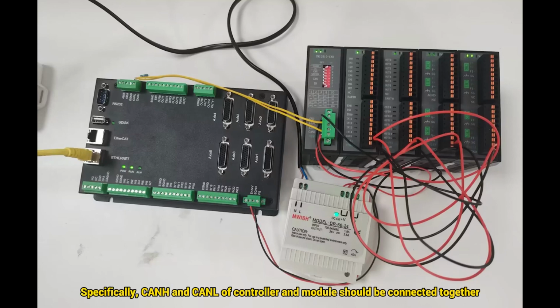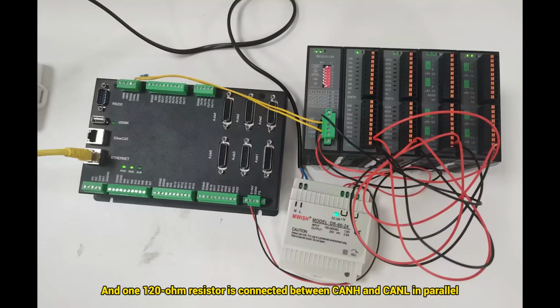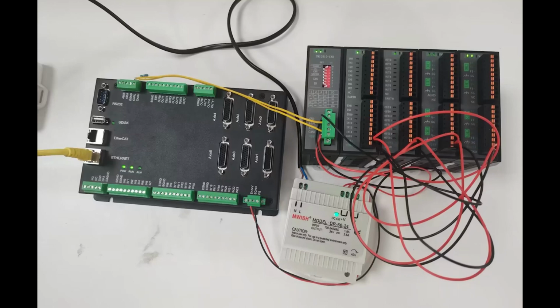Specifically, CAN-H and CAN-L of the controller and module should be connected together. And one 120 ohm resistor is connected between CAN-H and CAN-L in parallel. Then Code 8 should be dialed as on.